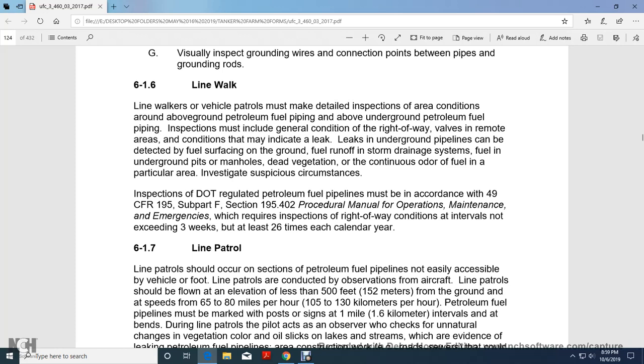Inspection of DOT regulated petroleum fuel pipelines must be in accordance with Title 49 CFR 195 Subpart F, Section 195.402, procedural manual for operations, maintenance and emergencies, with the requirements for inspection of the right of way at intervals not exceeding 3 weeks, but at least 26 times each calendar year.